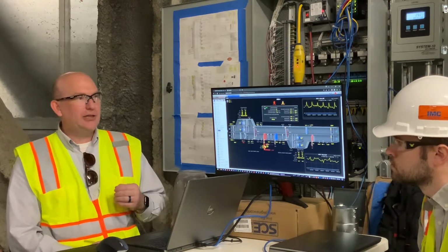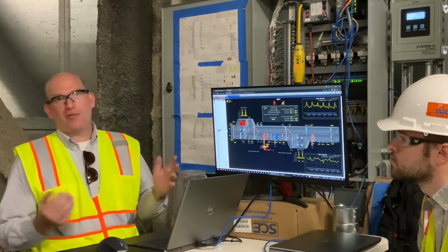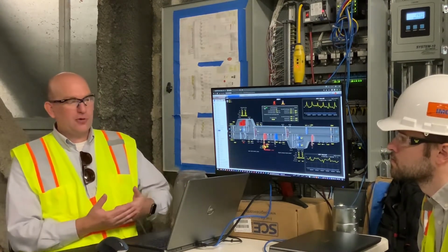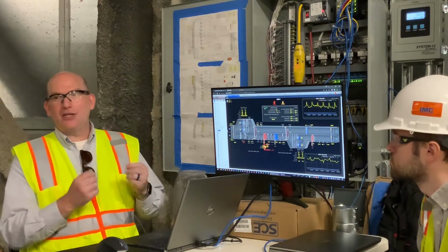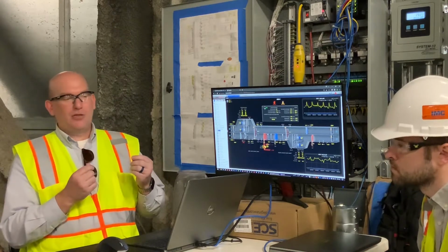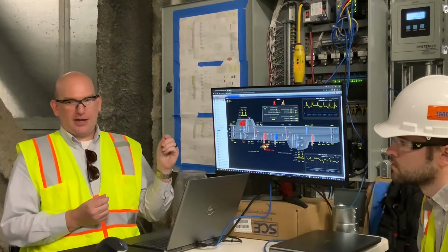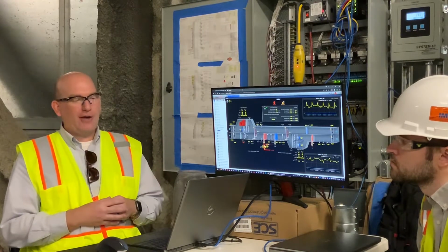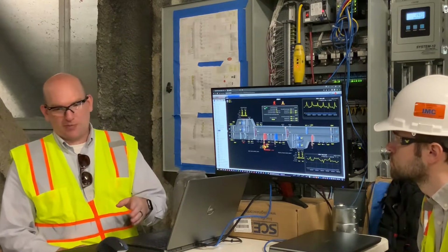All 4 of the air handlers are designed to run at the same time all the time. There's no staging, there's no modulation, there's no we're gonna turn one off because there's no demand in the building. All 4 run all the time. Fans modulate up and down in unison. There's a common signal that is spread across all of the air handlers, and all air handler speeds should be locked together, both on the exhaust and on the supply.